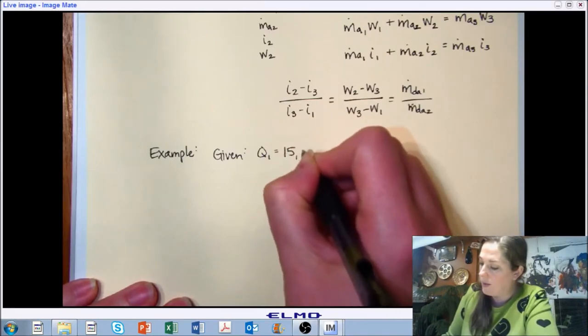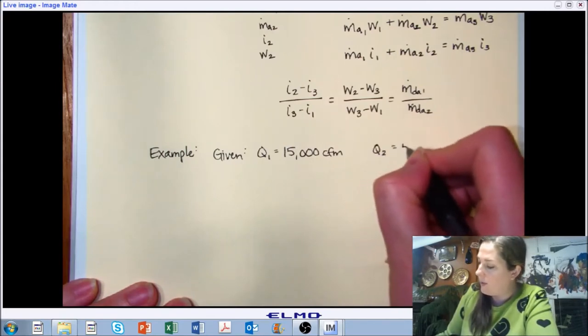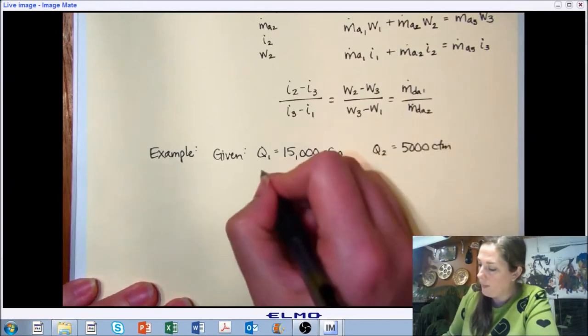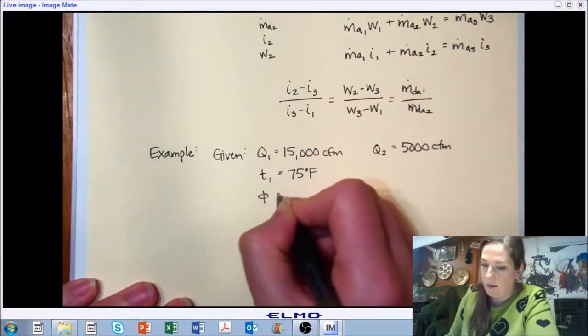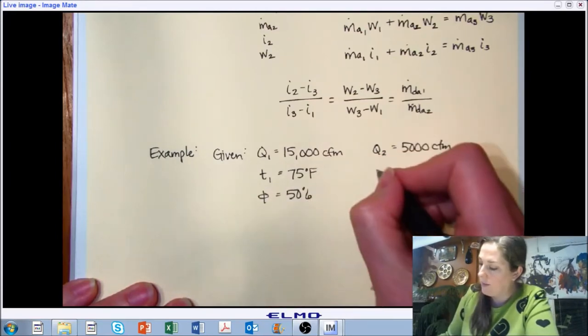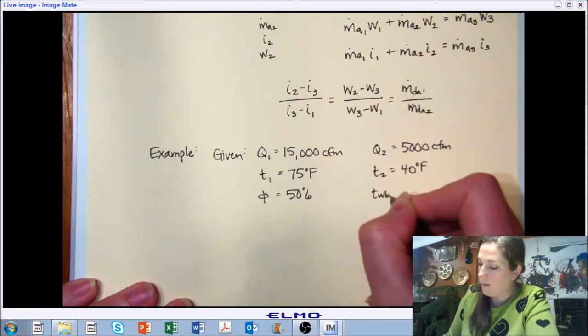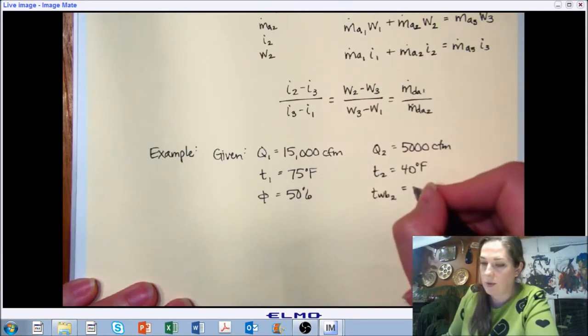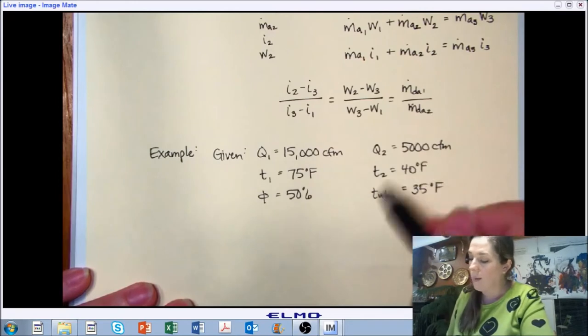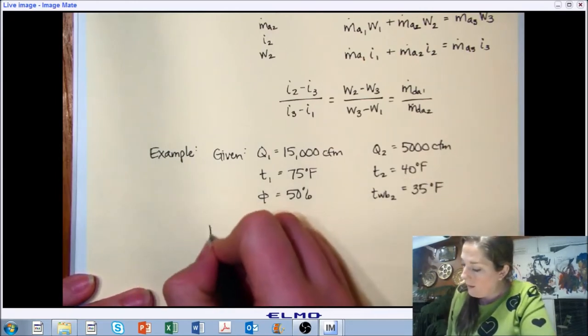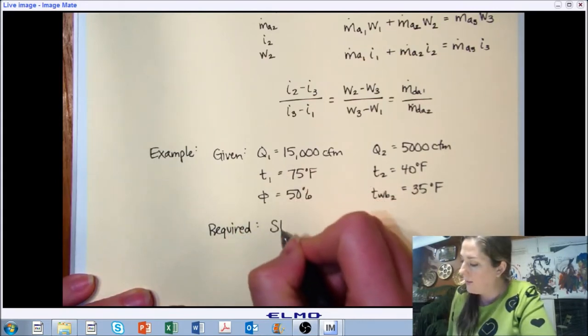So we're given two airstreams. One of them is 15,000 CFM. The other is 5,000 CFM. One is at 75 degrees Fahrenheit and 50% relative humidity. The other is at 40 degrees Fahrenheit. And just to trip us up, we have a wet bulb temperature instead of a relative humidity, but that's okay. We know how to deal with that because all we need is two properties to get all the other properties of a state point.